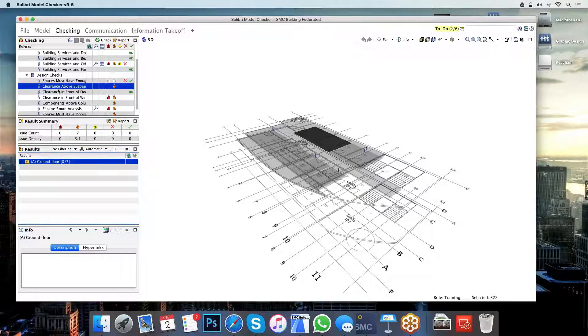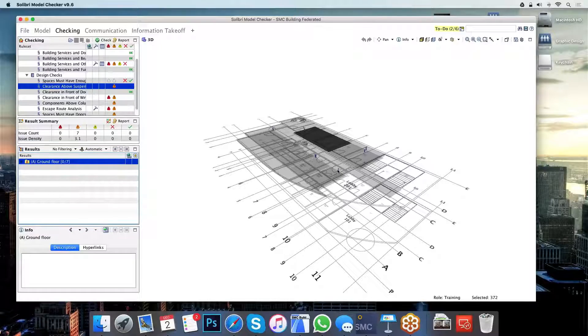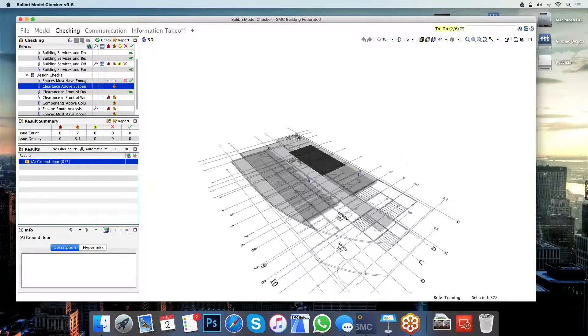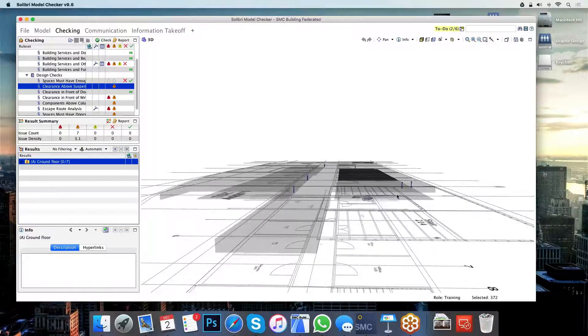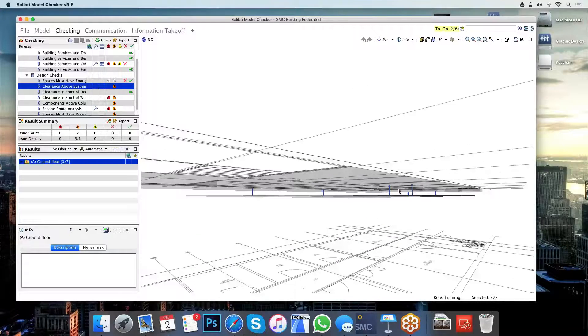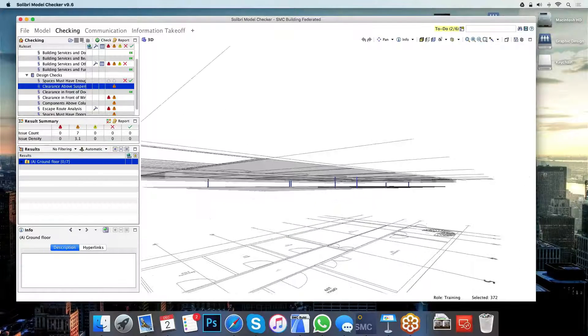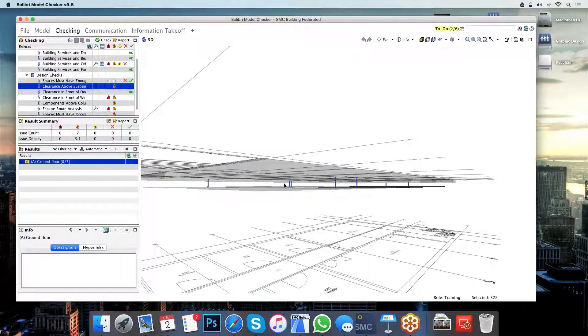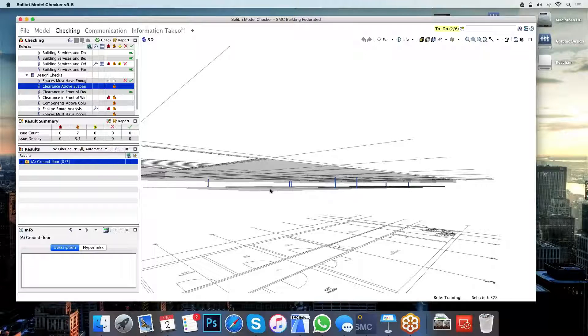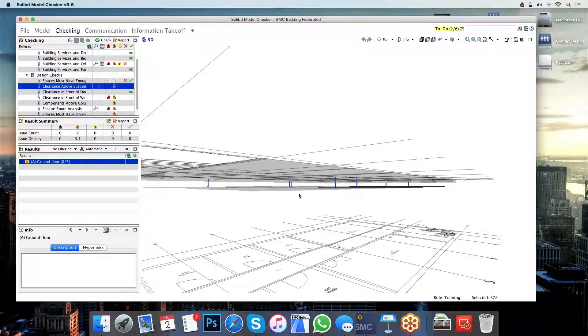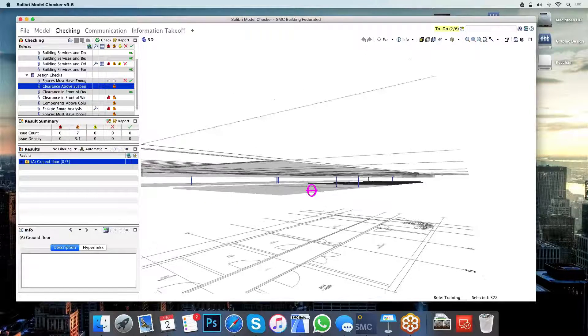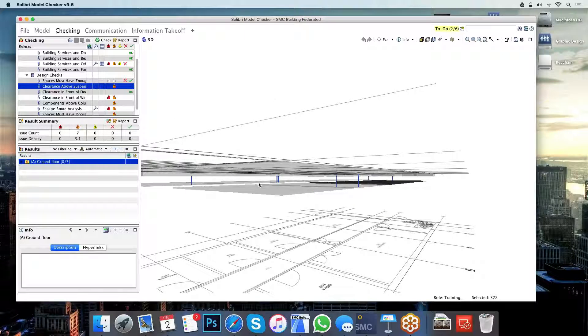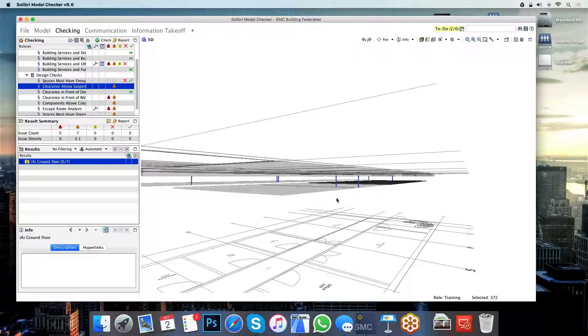The next issue I'm going to highlight here is the clearance above the suspended ceiling here. What Solibri is telling me here is that there is not enough space, according to my own rules, between the underside of the slab and the top of the suspended ceiling below that slab. Now this isn't a particular issue in the sense that if we go on site with this design, this can still be built.